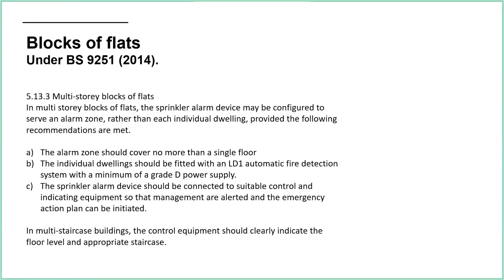Fair enough. The individual dwelling should be fitted with an LD1 automatic fire detection system with a minimum of grade D power supply. I'm not an expert on that, but I had a quick Google, and essentially it's a simple, standard smoke alarm system, but it's mains powered. It's a very standard design, but it's got to be there. That's the key thing. I would say if at any time that system goes offline or gets stripped out, then you're not fulfilling this code criteria. So that's something to bear in mind.